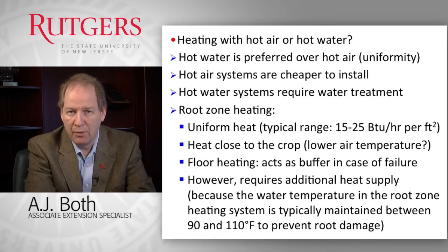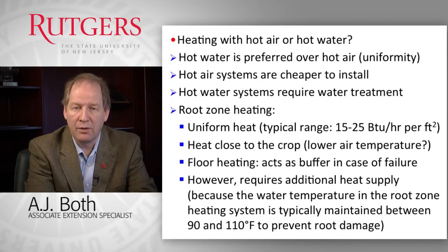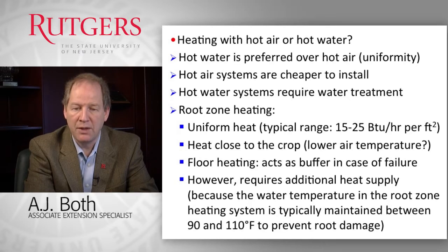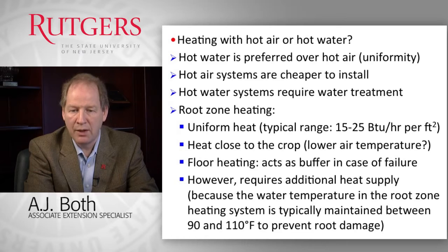One of the questions growers ask is which is better — a hot air heating system or a hot water system? I recommend hot water systems because of the increased uniformity in heat distribution. However, hot air systems are typically cheaper to install, which can be a major consideration. Hot water systems also often require water treatment because dissimilar metals in the various components can cause corrosion and premature failure if the water is not treated properly.